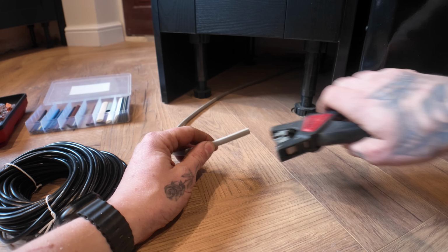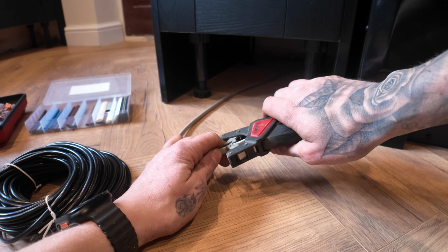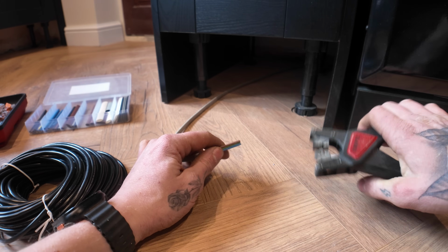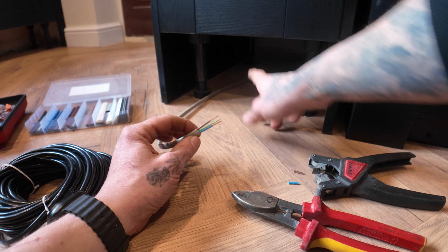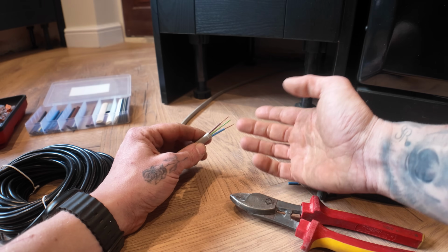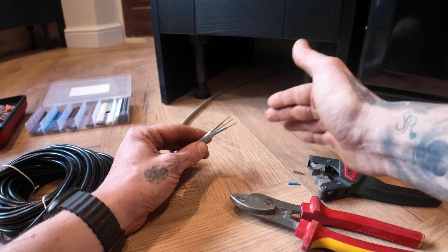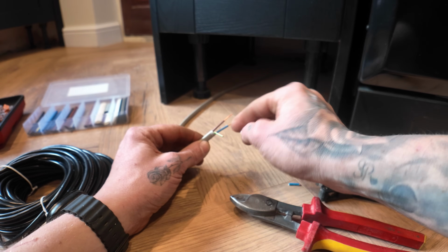Okay. The cable's all a bit excessive underneath, but to be honest with you, I am not, for the life of me, going to cut any cables shorter. They're just going to be left in a nice coil. I'm going to cable tie some of the cable if it's too excessive to the underside, but being 24 volt coming down, there is a CPC within the cable. We're not using it. It won't even be connected that end because this side will be 24 volts.